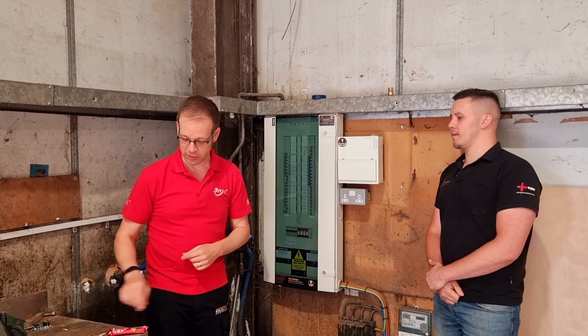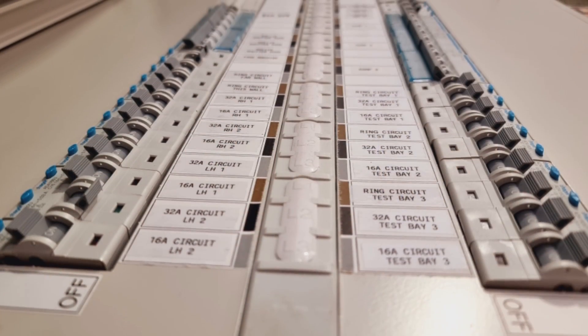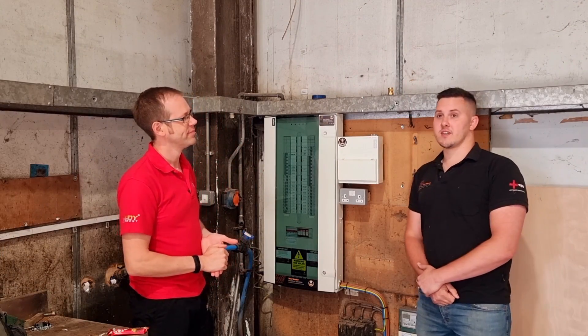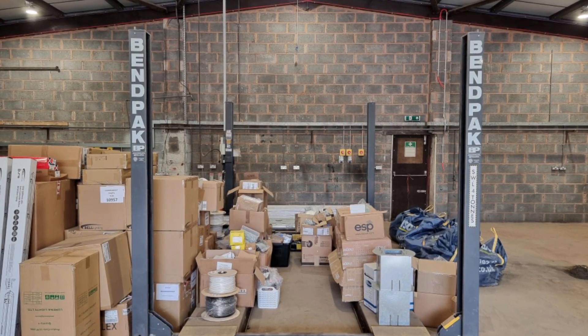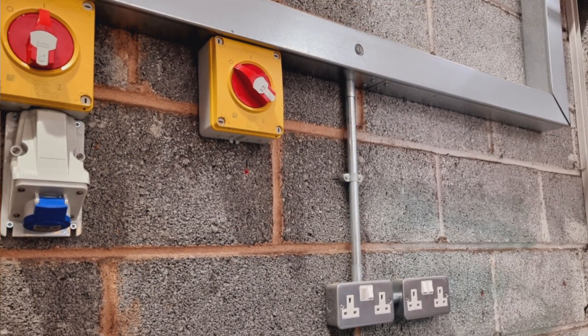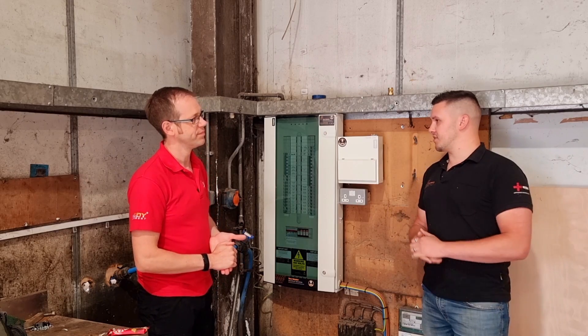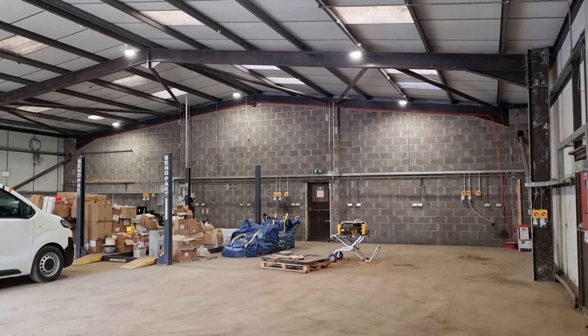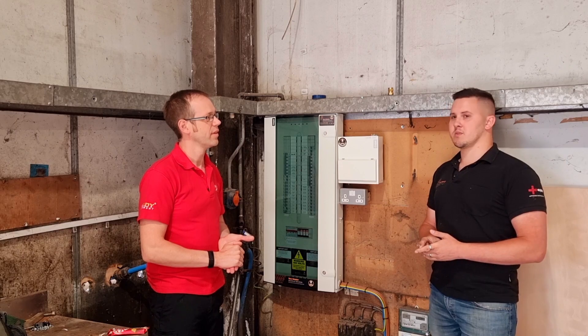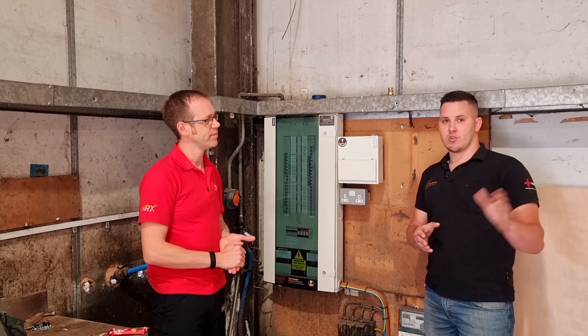We've come over to the distribution board — it's a very full board for what isn't a huge space. There's a lot going on: three servicing bays for motorhomes, each with a 32 amp and a 16 amp single-phase supply, as well as a three-phase supply for future vehicle ramps. There's also a ring main in each bay consisting of six twin sockets for angle grinders and whatever they may need. We've also got 32 amp and 16 amp supplies around the rest of the workshop for charging leisure batteries on the motorhomes — we've tried to make it as versatile as possible.